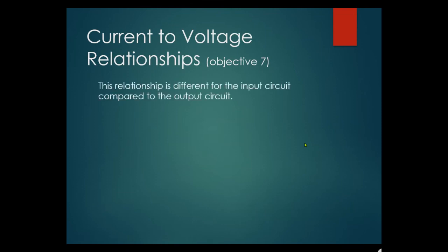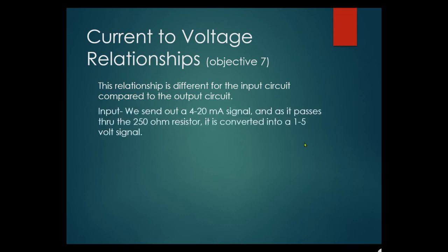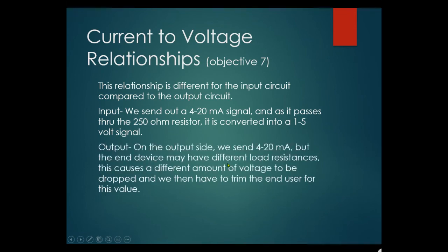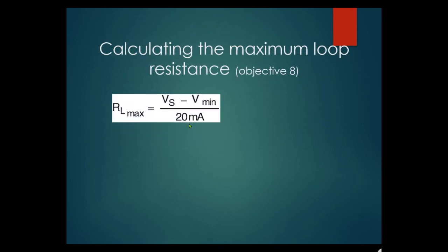Objective seven — current, resistance, and voltage relationships: this relationship differs between the input and output circuits. If a 4 to 20mA signal passes through a 250 ohm resistor, it's converted to 1 to 5 volts. On the output side, the end device may have different load resistances causing different amounts of voltage to be dropped, and you then have to trim the end user for that value. Maximum loop resistance: RL max equals voltage supplied minus voltage minimum, divided by 20mA.